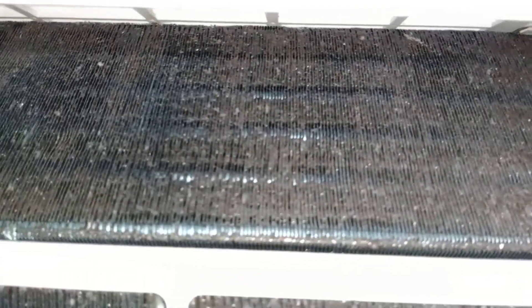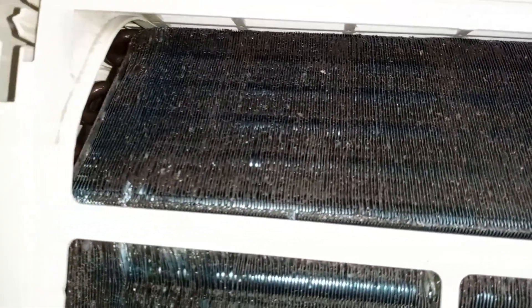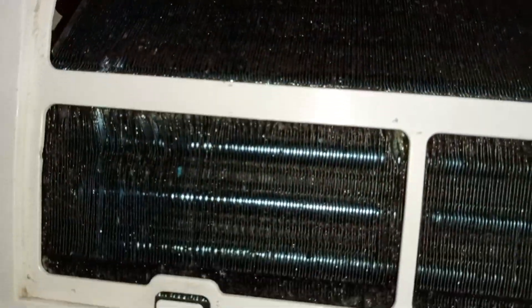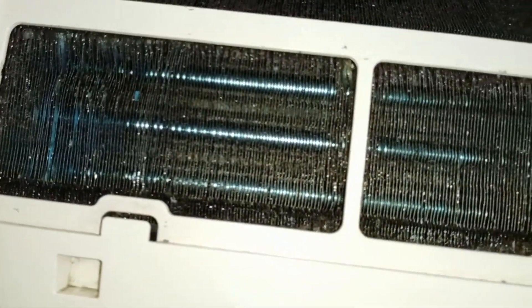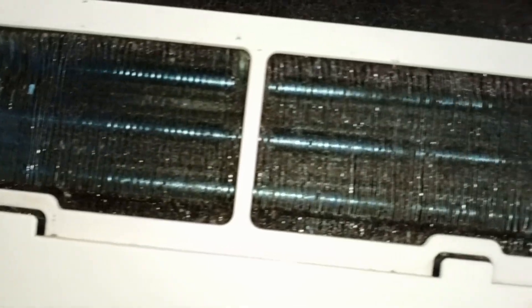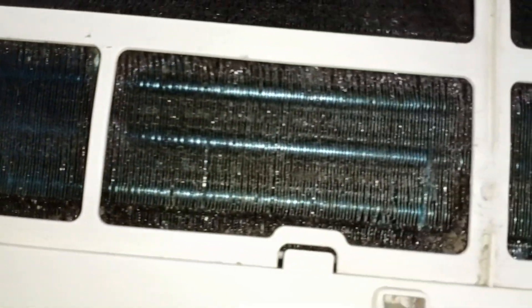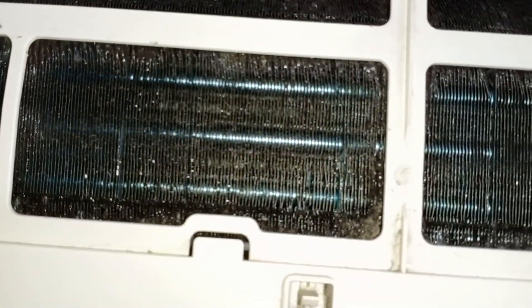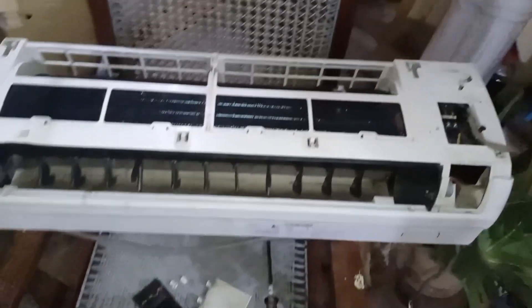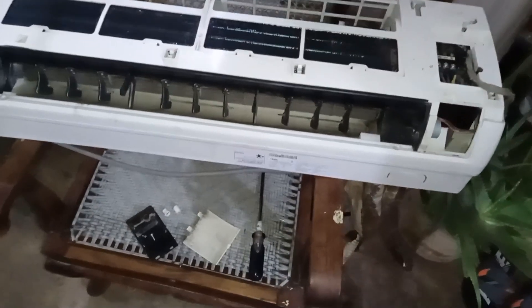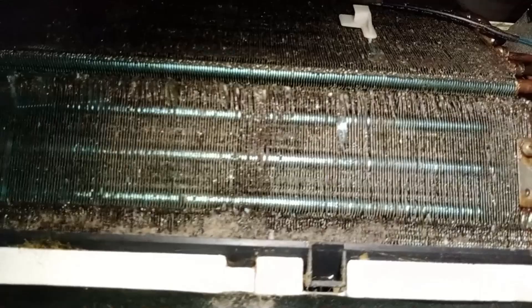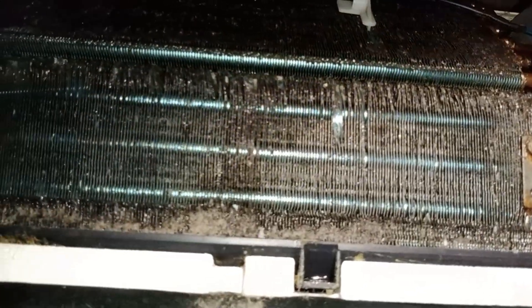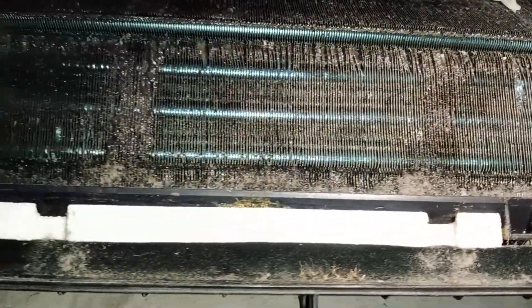Upon examination, all the fins of the evaporator were blocked. This severe blockage has drastically reduced the blower's suction capacity, which is why the fan is making unusual noises during operation. Now I have removed the indoor unit from the wall for cleaning. As we started dismantling it, the dirt became more evident.